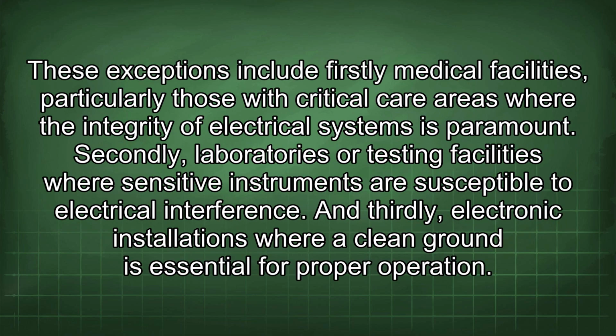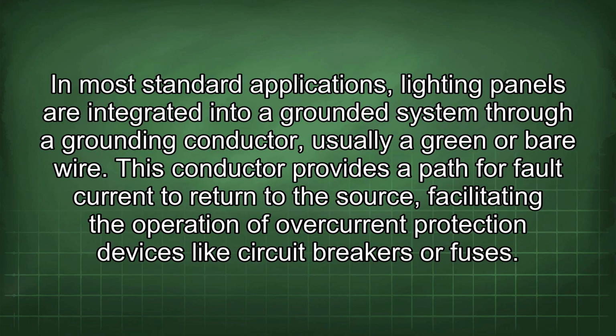These exceptions include, firstly, medical facilities, particularly those with critical care areas where the integrity of electrical systems is paramount. Secondly, laboratories or testing facilities where sensitive instruments are susceptible to electrical interference. And thirdly, electronic installations where a clean ground is essential for proper operation. In most standard applications, lighting panels are integrated into a grounded system through a grounding conductor, usually a green or bare wire. This conductor provides a path for fault current to return to the source, facilitating the operation of overcurrent protection devices like circuit breakers or fuses.